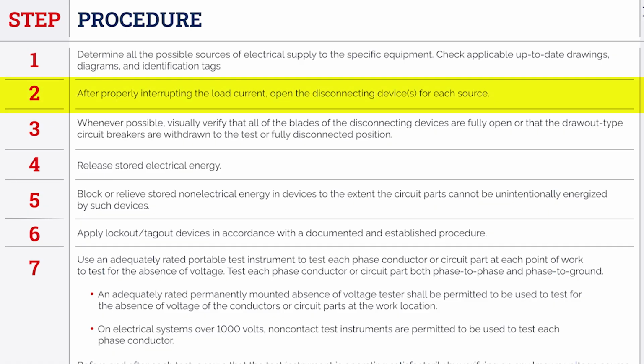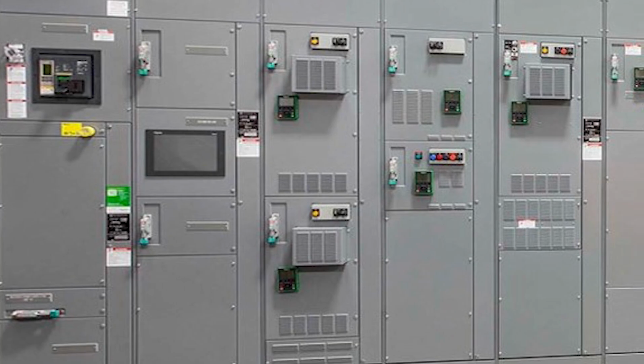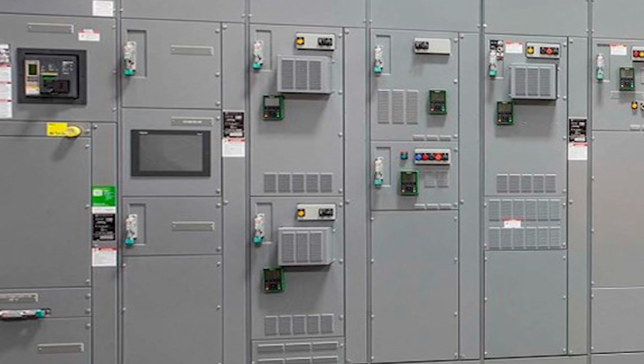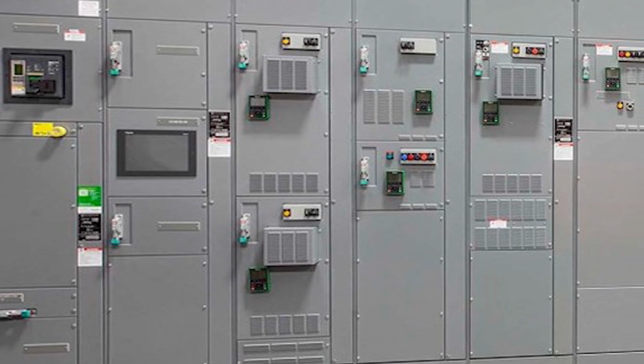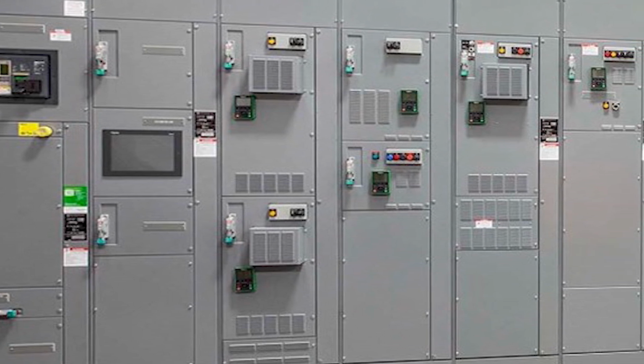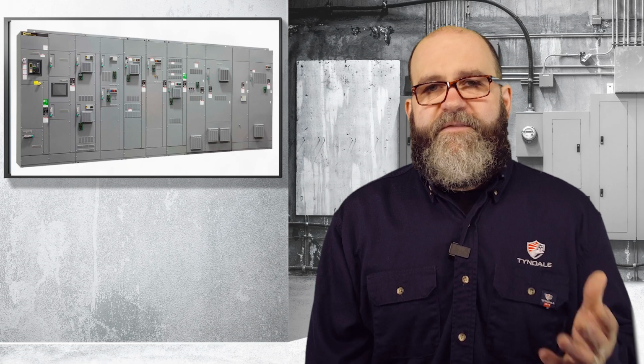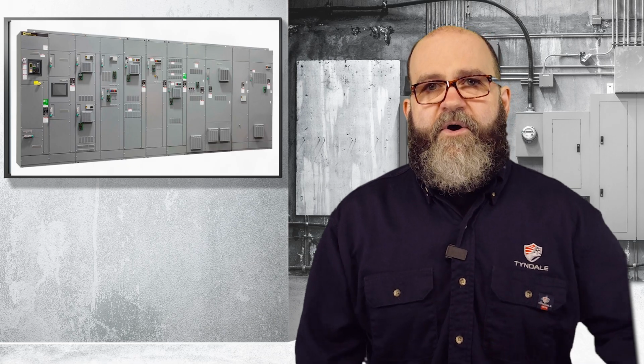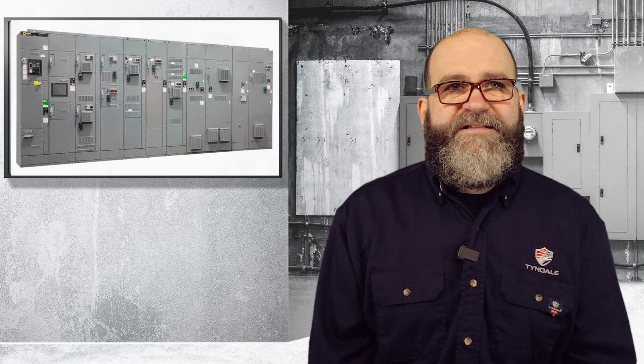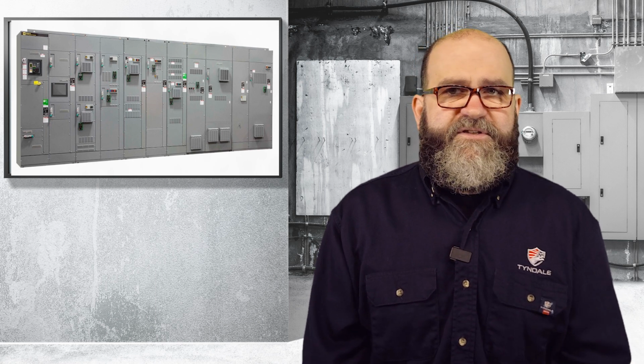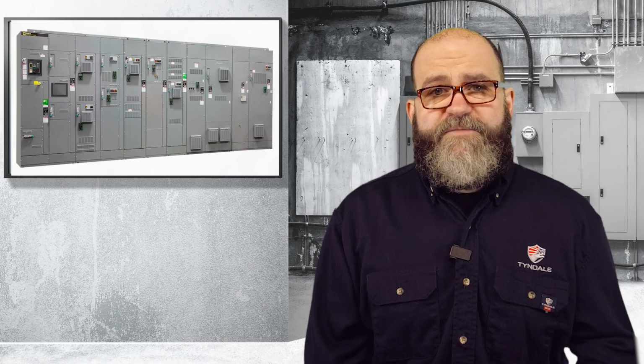Step 2 tells us that after properly interrupting the load current, open the disconnecting devices for each source. An example might be, say, a motor control center. You wouldn't want to turn off the main breaker on an MCC without turning off the individual loads. You want to click off the individual branch loads, then kill the main, do your work, turn the main on, bring that piece of equipment on slowly but surely. Operating a main switch under load, even if it's load rated, is never a good idea if you can avoid it. This can increase risk of damage to the switch contacts, as well as a possible arc flash.